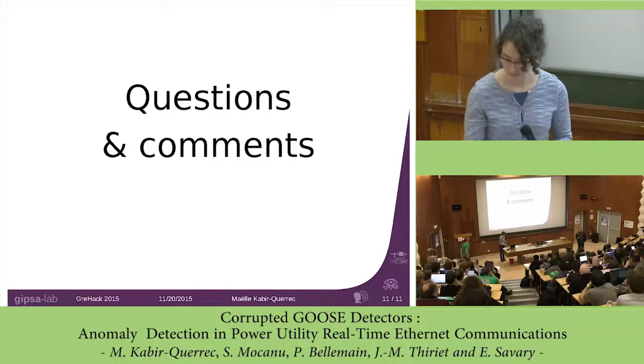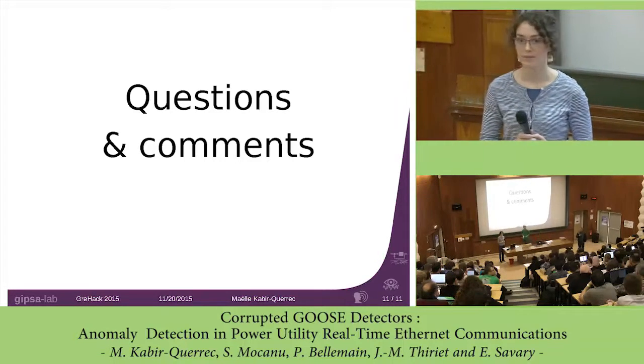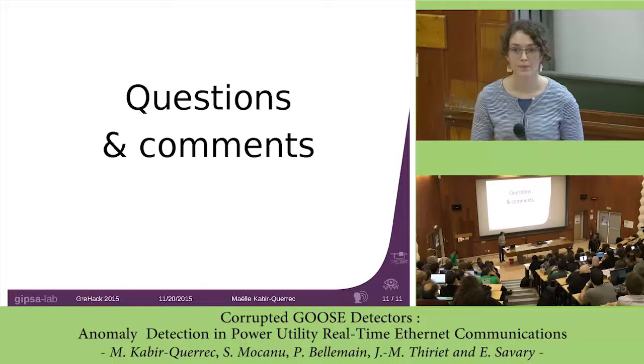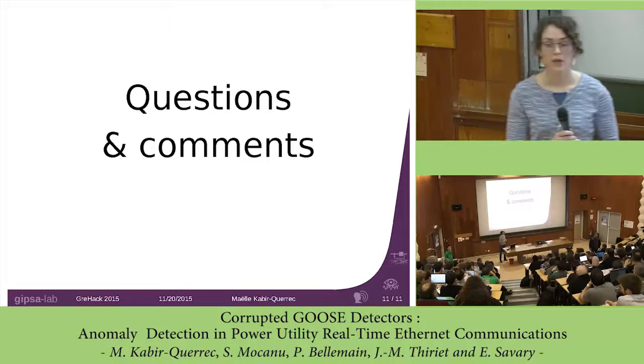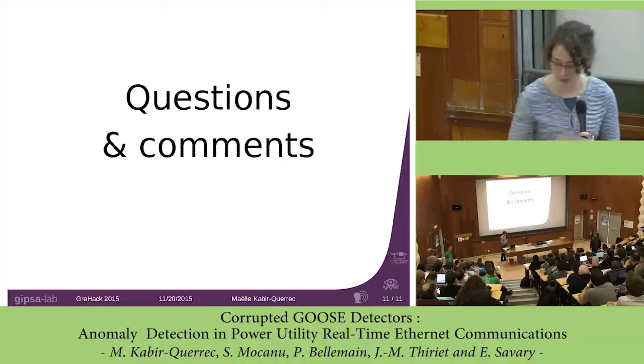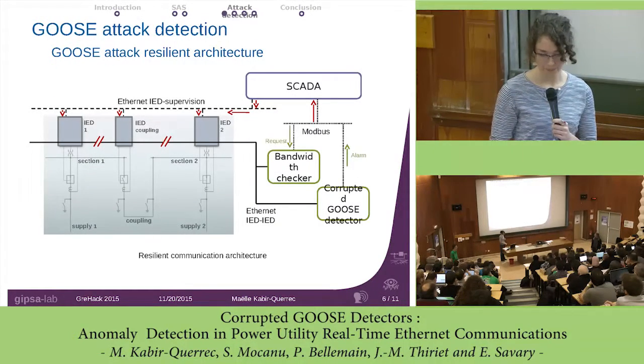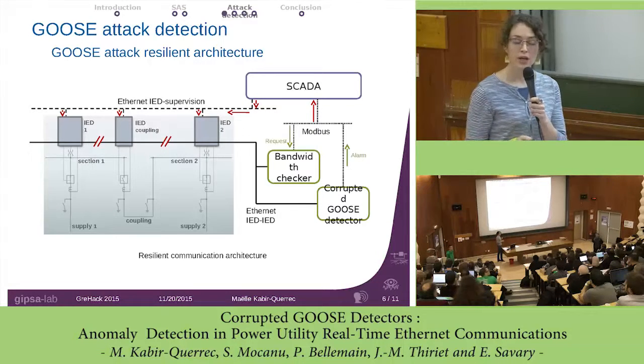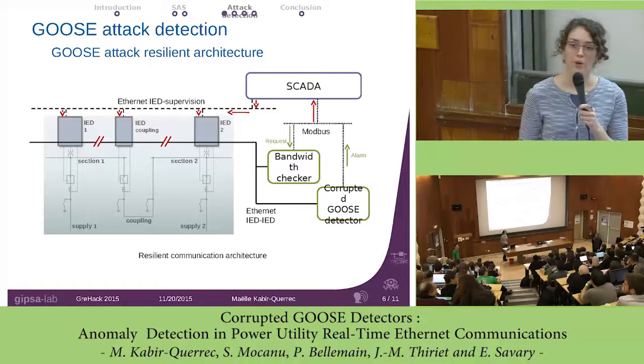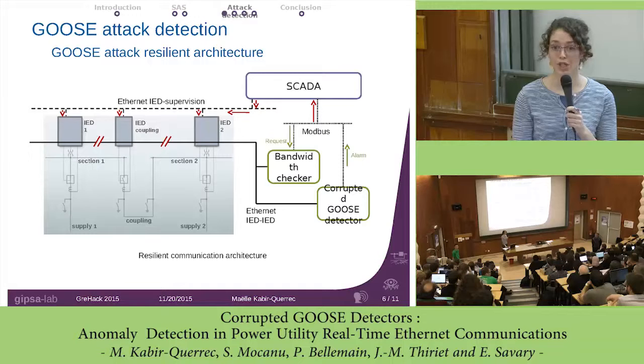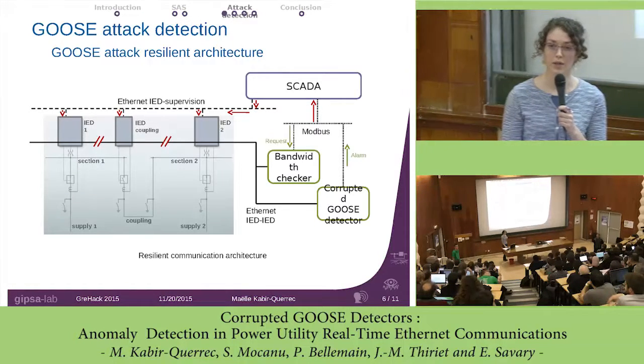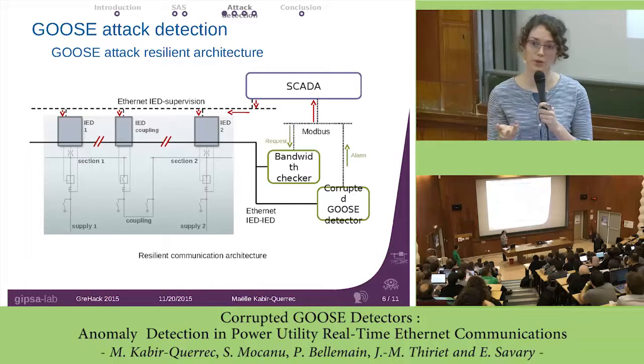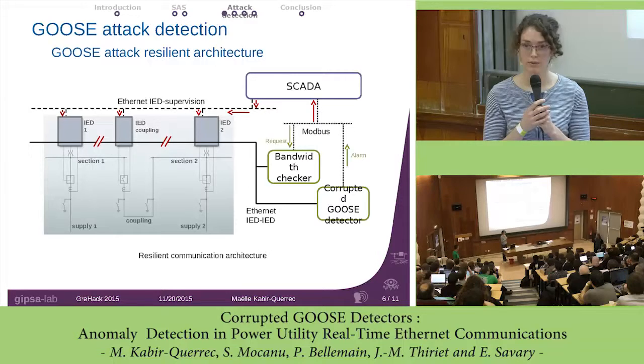Question from the audience: How do you stop the GOOSE communication after the attack is detected? Answer: When I say I prevent IEDs from communicating with each other, it's in the program — you can program logic into those devices. When they receive the alarm from the supervision, they switch programs. In the new program they execute, there is no involvement of GOOSE messaging.